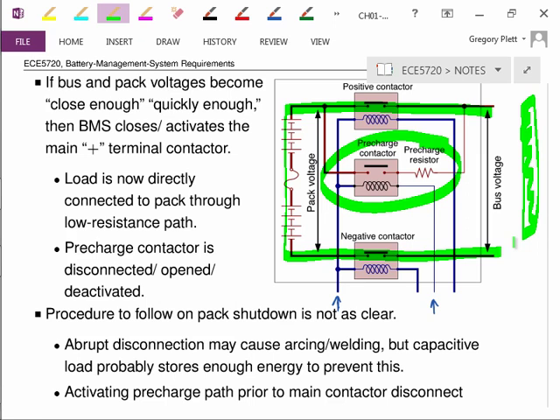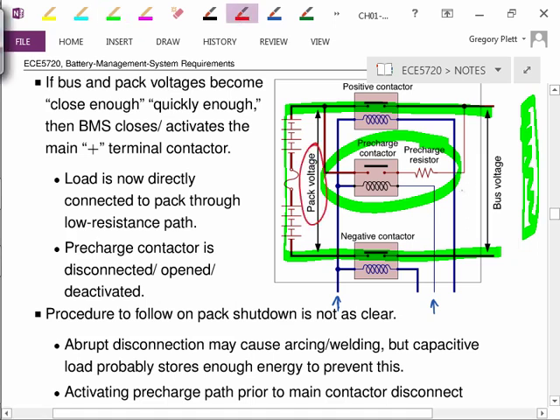But normally what you would do is monitor the bus voltage and pack voltage during the precharge, and when they get close enough, you close the positive contactor. To do that, you need a pack voltage sensor and a bus voltage sensor. We already measure all of the cell voltages, so you might add them up simply to get a pack voltage, or alternately you could have a high voltage A to D that also measures the pack voltage as a kind of backup sensor.